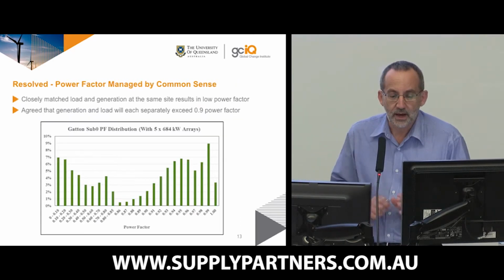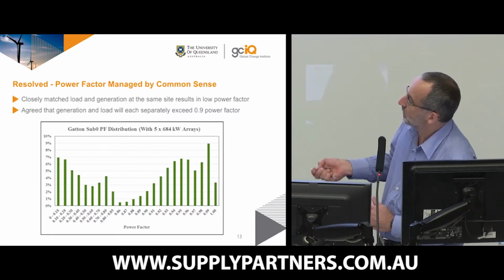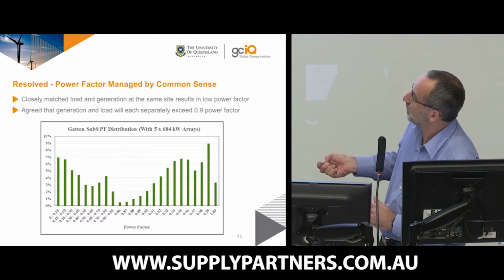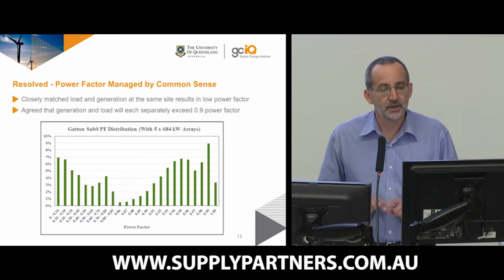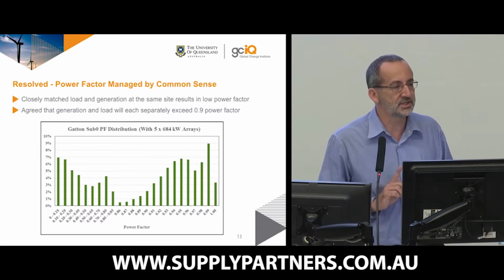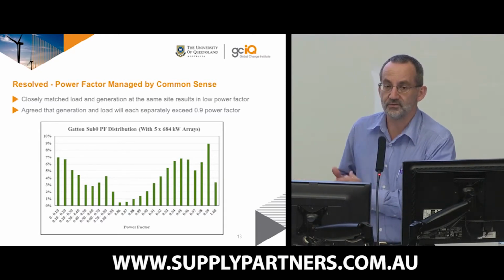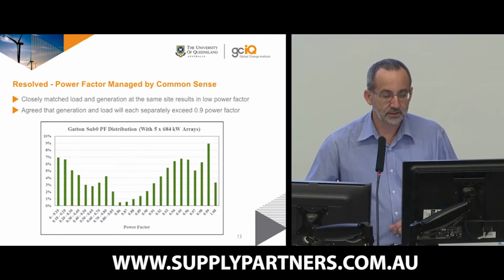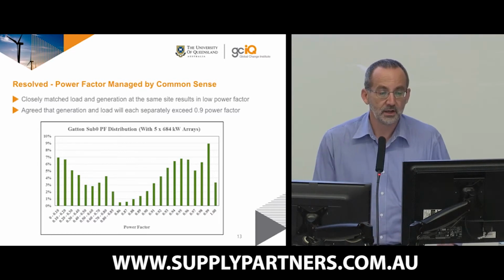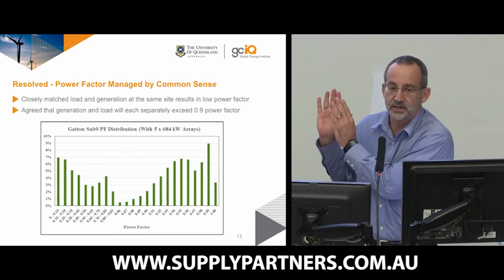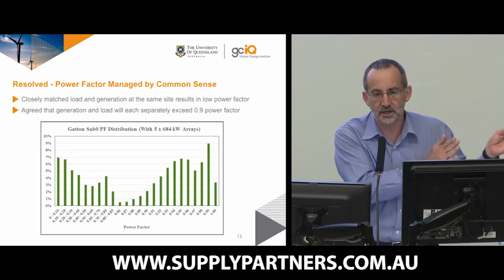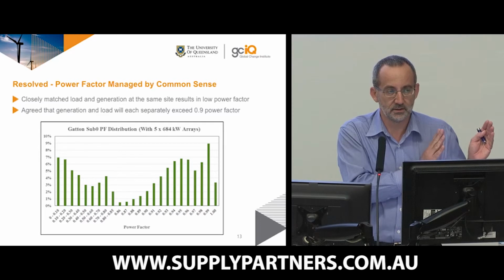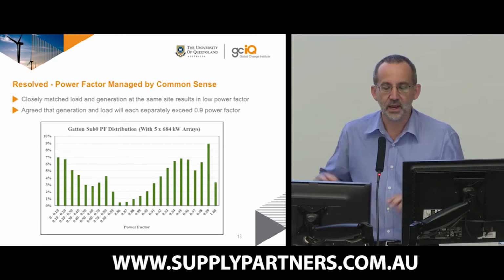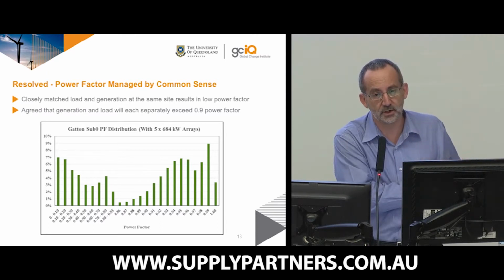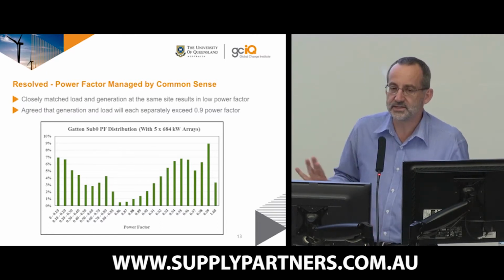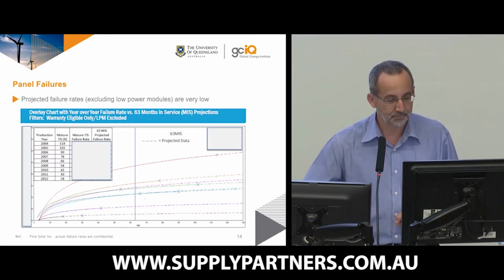The other one was power factor. The studies we did showed that for quite a lot of the time, we would run at power factors well below the 0.9 that's required under the legislation. The legislation does, however, give the utility discretion to allow for lower values. We argued that battle, and we ended up agreeing that they would look at the power factor associated with our generation and the power factor associated with our load as separate things. So we will control both of those within 0.9, even though the total will become quite poor at times. But the fact that it's quite poor is insignificant because it's fairly low magnitudes.